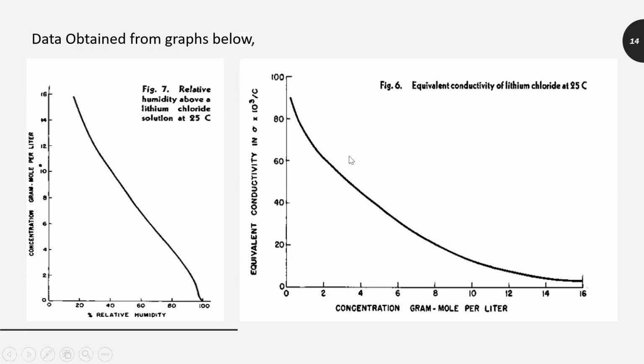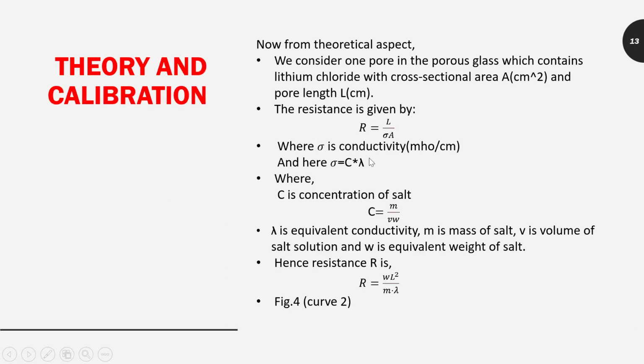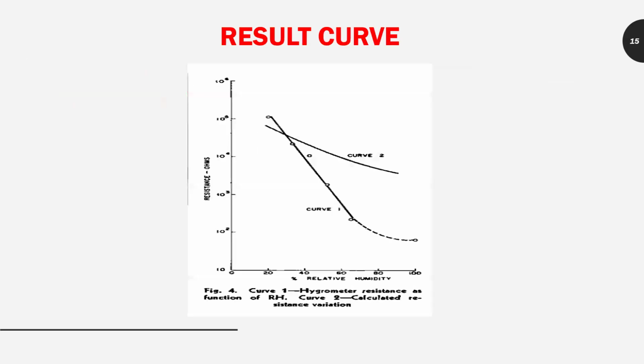Here we get equivalent conductivity from the concentration. This is the data at 25 degrees Celsius. We can get equivalent conductivity, and at that concentration, we can also get the relative humidity. When we substitute this concentration and conductivity, we also get the resistance. So now we can plot the values between resistance and relative humidity. This curve gives the theoretical relationship of resistance versus percentage relative humidity.